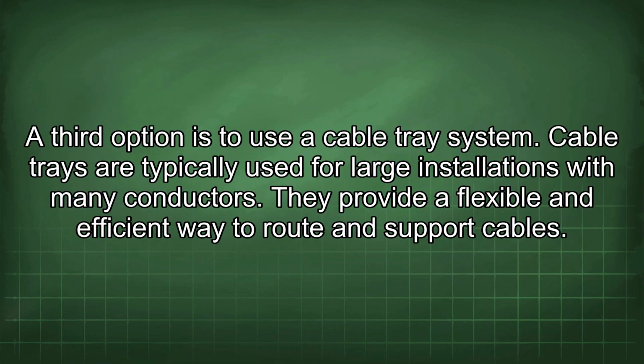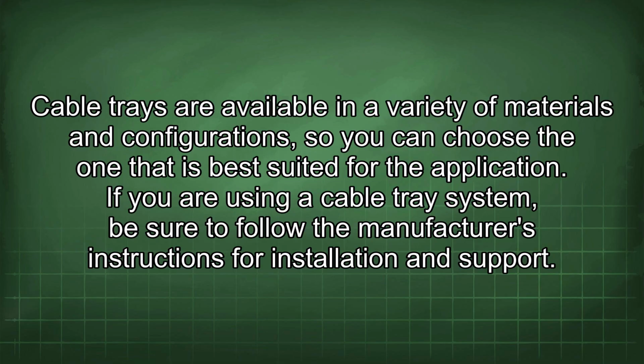A third option is to use a cable tray system. Cable trays are typically used for large installations with many conductors. They provide a flexible and efficient way to route and support cables. Cable trays are available in a variety of materials and configurations, so you can choose the one that is best suited for the application. If you are using a cable tray system, be sure to follow the manufacturer's instructions for installation and support.